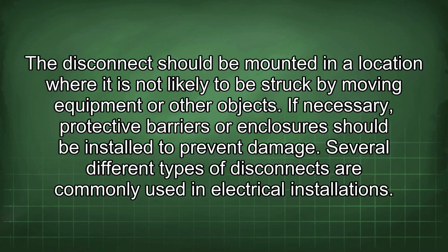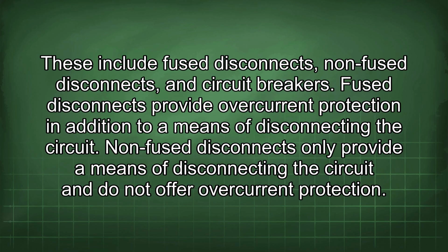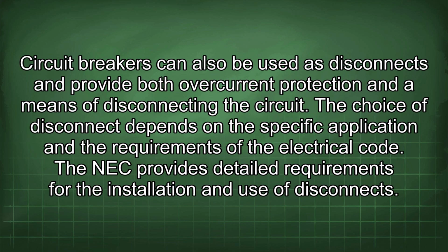Several different types of disconnects are commonly used in electrical installations. These include fused disconnects, non-fused disconnects, and circuit breakers. Fused disconnects provide overcurrent protection in addition to a means of disconnecting the circuit. Non-fused disconnects only provide a means of disconnecting the circuit and do not offer overcurrent protection. Circuit breakers can also be used as disconnects and provide both overcurrent protection and a means of disconnecting the circuit. The choice of disconnect depends on the specific application and the requirements of the electrical code.